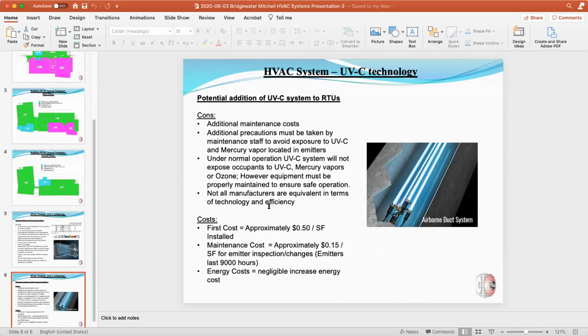We looked at the costs. It would add approximately 50 cents a square foot for an installed cost. On a yearly basis, about another 15 cents a square foot. The emitters have to be changed every 1, maybe 2 years. And a good thing is that there would be negligible increased energy costs, and some studies actually show some energy savings, because it's continually cleaning. Particularly when it's installed in the air handling unit, if it's cleaning the airstream, it's also cleaning the cooling coil and keeping its efficiency level high. So that would be a pro of the system.